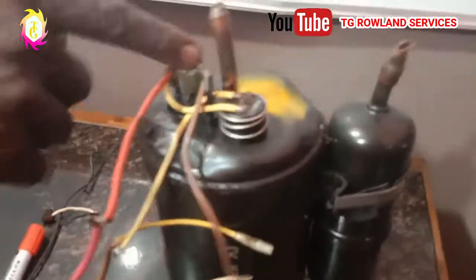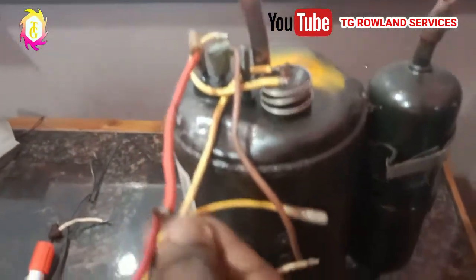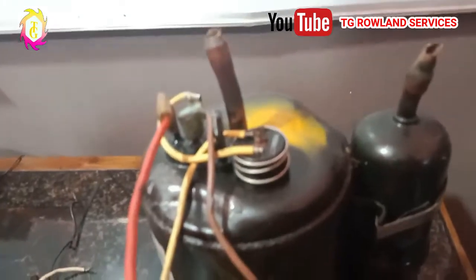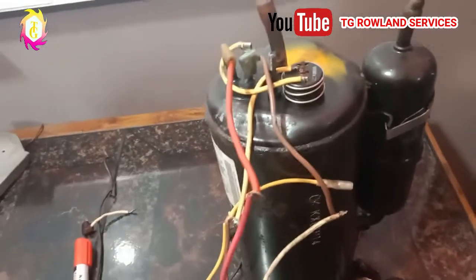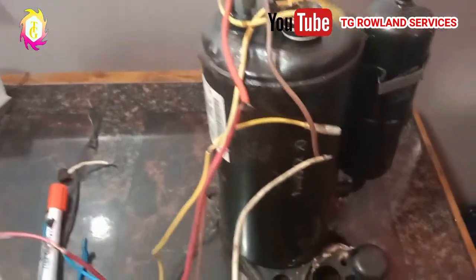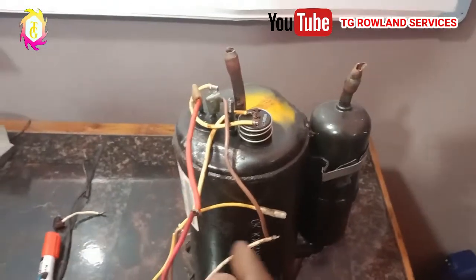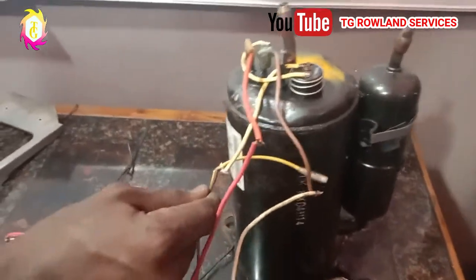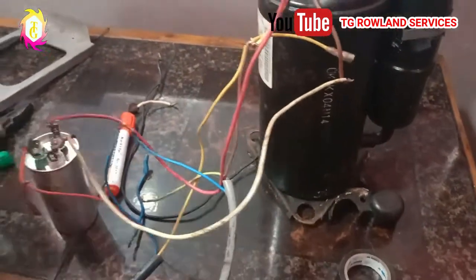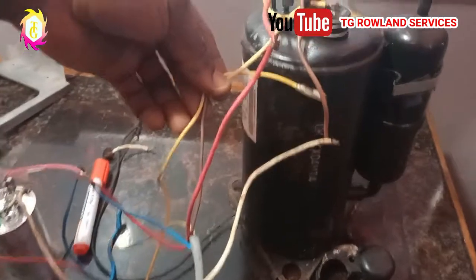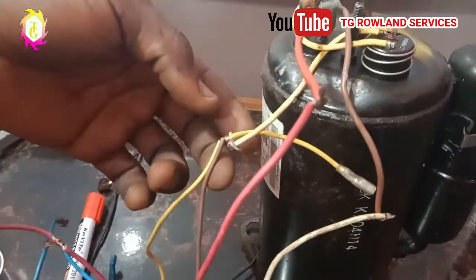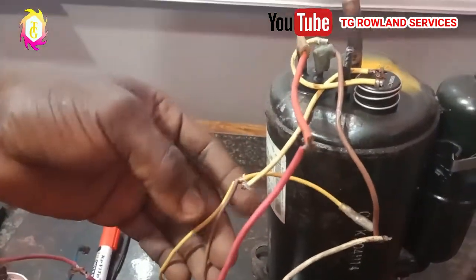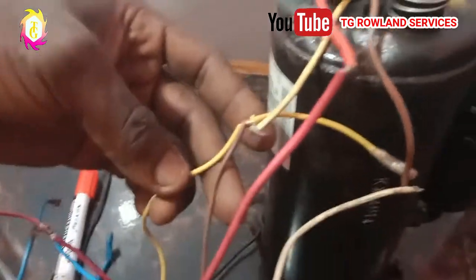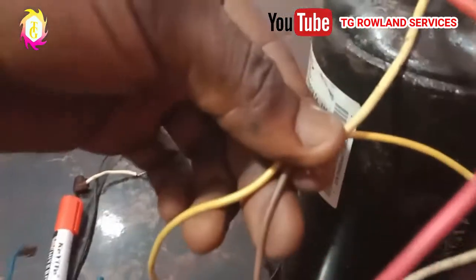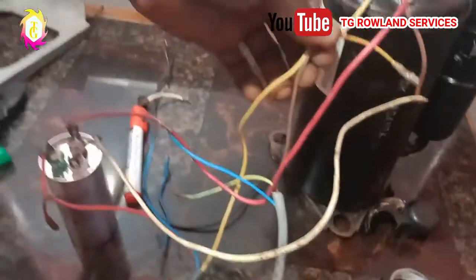This is common, running, starting. The common, being the yellow wire of this overload, has to be connected by the live wire. Watch it. This is the live wire of this cable. The red one is being connected to this, and this is the only place for the red wire, which is the live. We have to connect only the fan line here and the compressor line. This is the only one that can receive live.